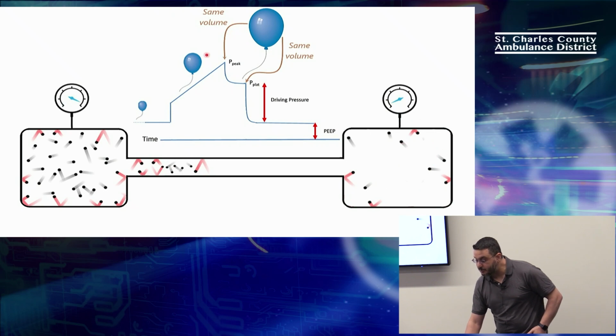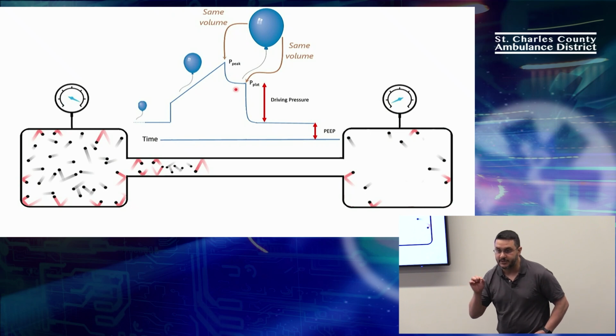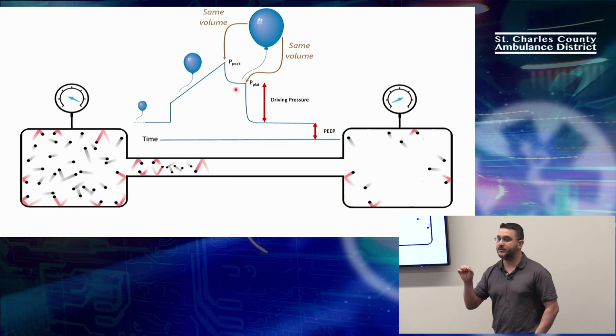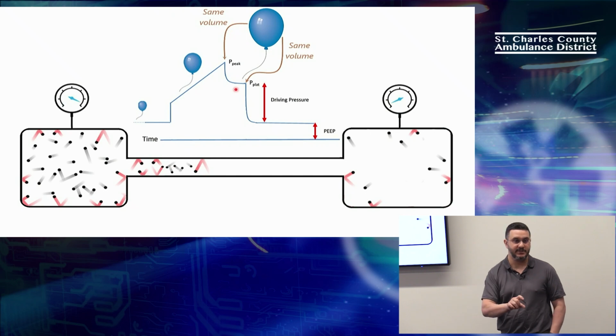Now remember what we said, the pressure in the ventilator, which is the peak pressure, is always higher than the lungs, or else there was no flow. So when you pause the breath, you get this thing called the plateau pressure, and this is one of the most important pressures there is. This is what tells you, should I increase PEEP or not?